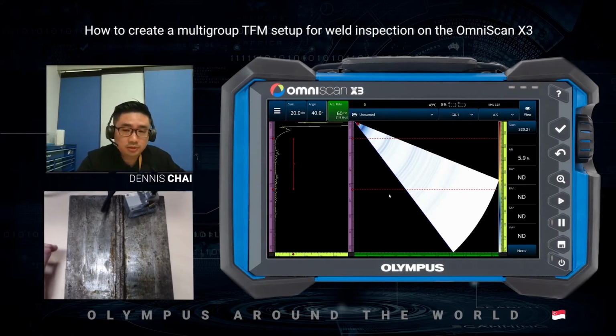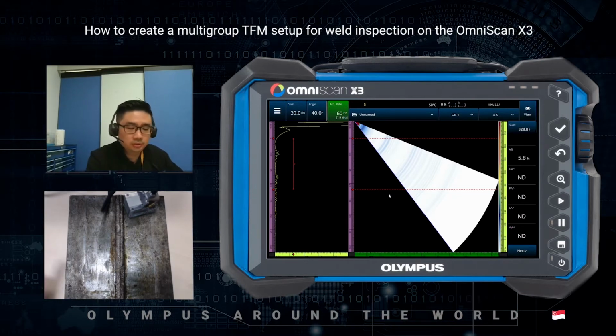I'm the application specialist, and today I would like to do a demonstration on how to set up multi-group TFM for inspection. So we've got the X3 over here, and we've got a weld sample with a 5L32 SA32 probe.